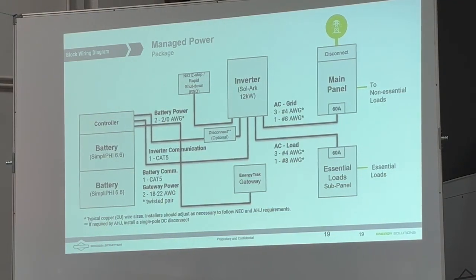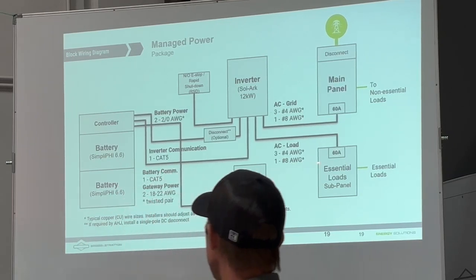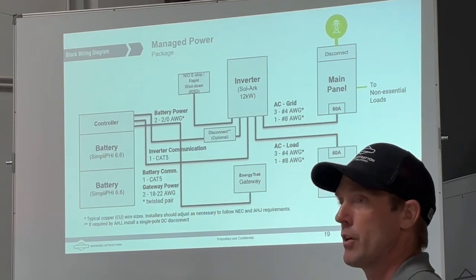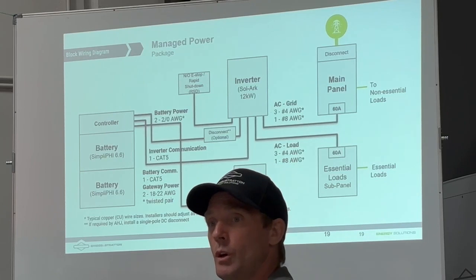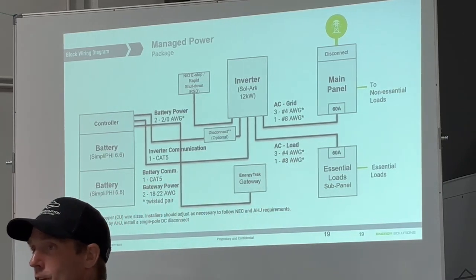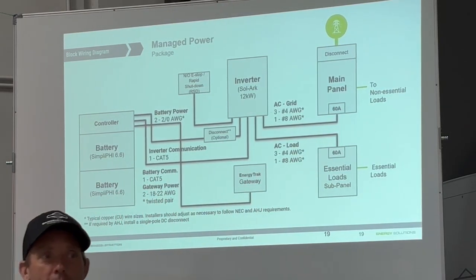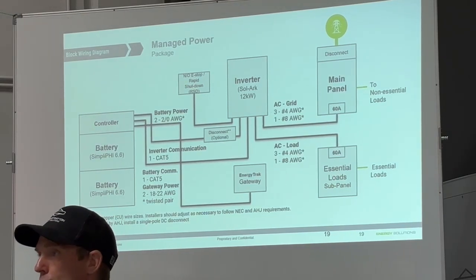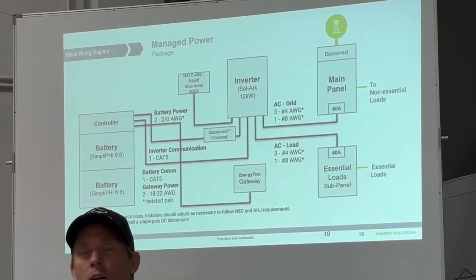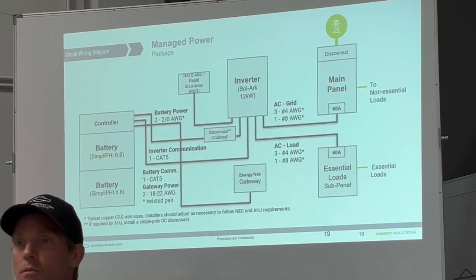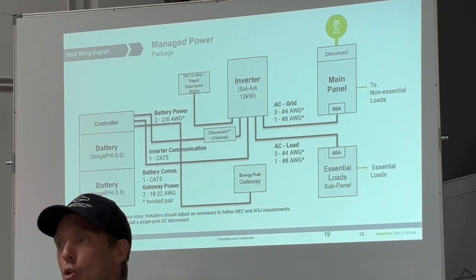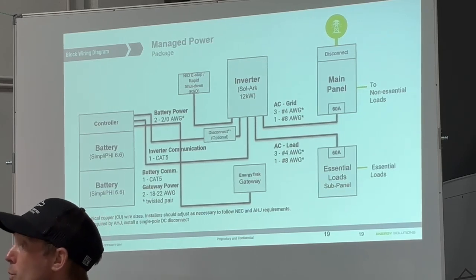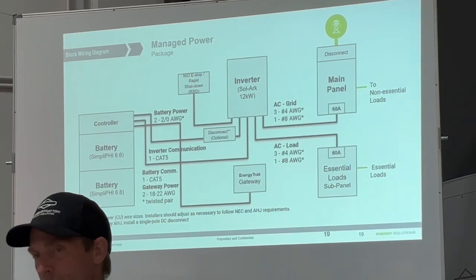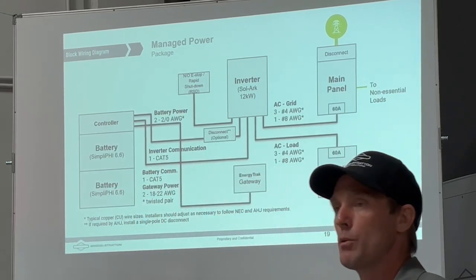Now you could come into that load center and change the bus bars and upgrade those to solar bus bars. But we are not limited in a 100 amp situation to just putting a 20 amp breaker on there as you would be with some other inverters. Why? Right? Does anybody know the acronym? Because I'm kind of blanking on it right now. But the Sol-Ark inverters are power control rated, so you can limit the amount of power going back onto bus bars. So if you've got a PCS, power control system, they limit the output, so you've got that output limitation with the Sol-Ark.